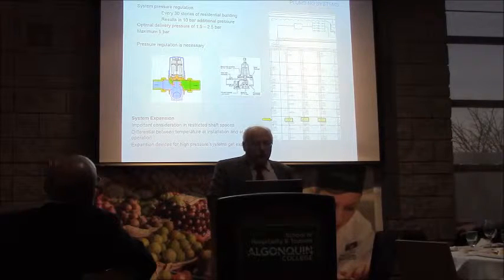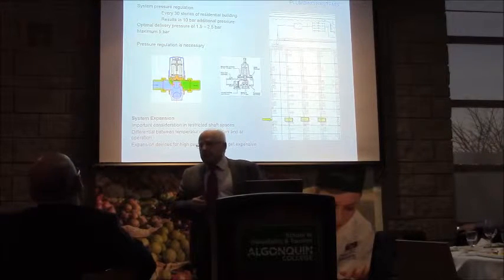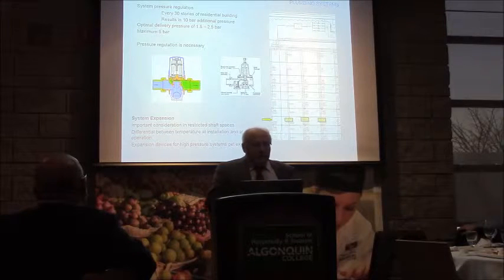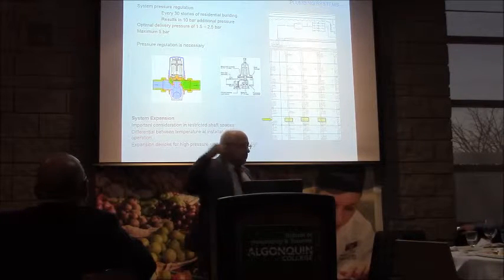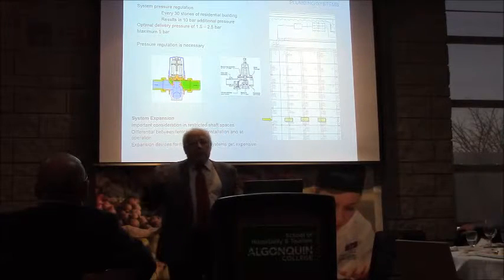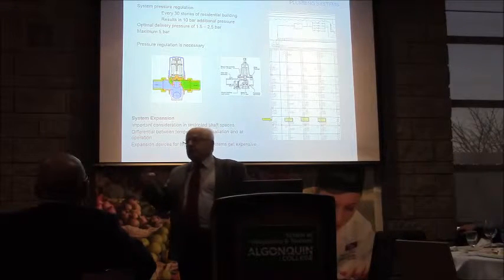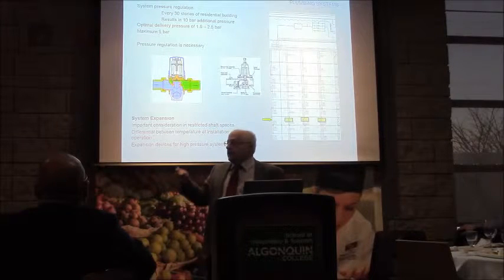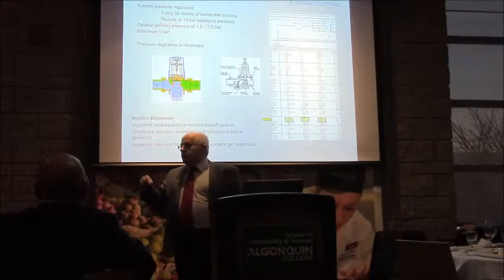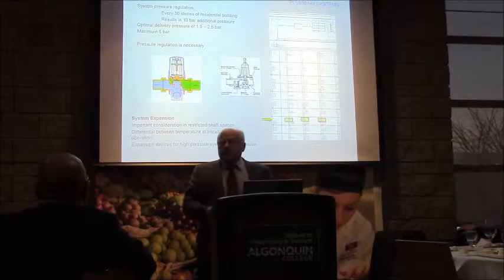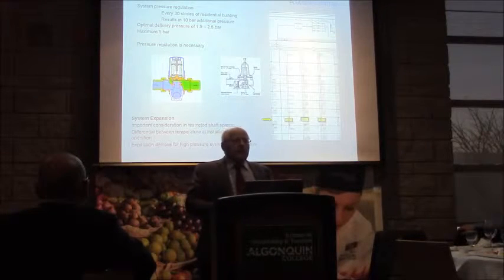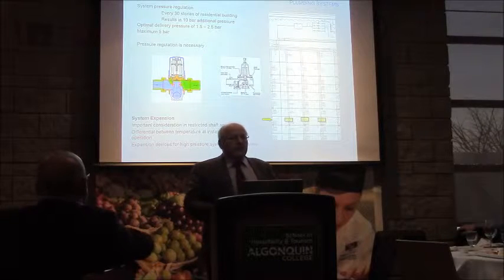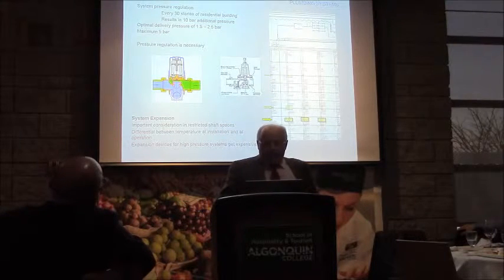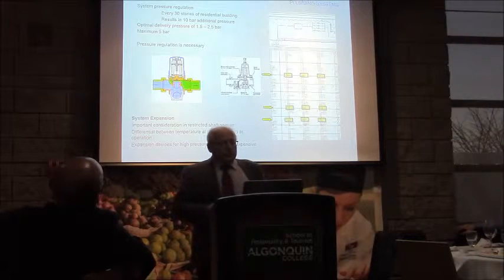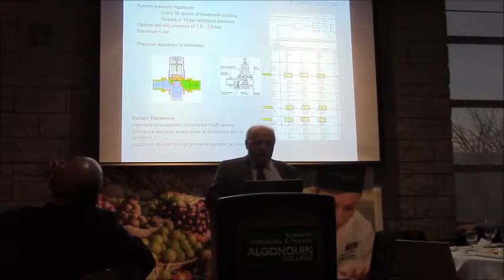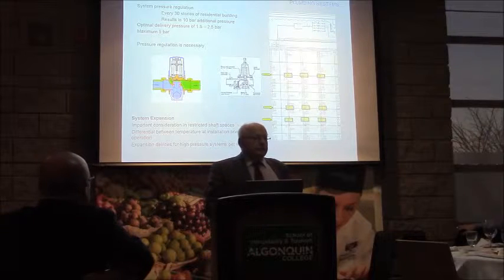Another aspect to any kind of vertical distribution, and this goes not just for plumbing but any of these systems, is expansion. Particularly in that part of the world, it's not just operational temperatures you have to worry about - it's the temperature difference between when it was installed and when it's actually being used. So while your operational temperature difference might be 40 to 70, it may have been installed when it was 130 degrees outside. So you got to worry about that, and we put in additional expansion joints - you toss them in like Smarties.